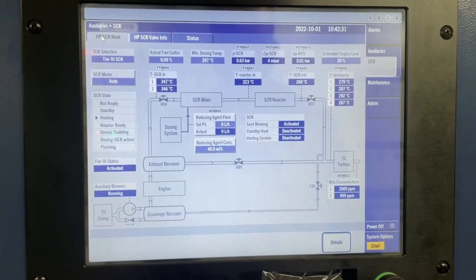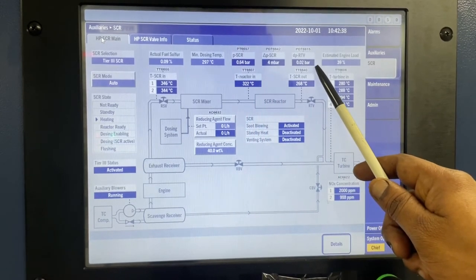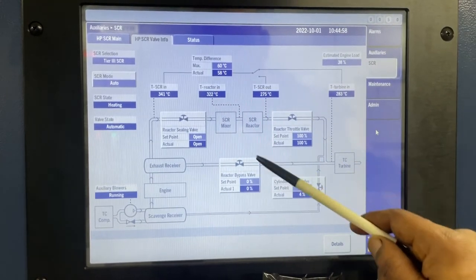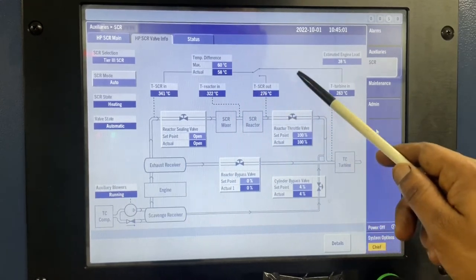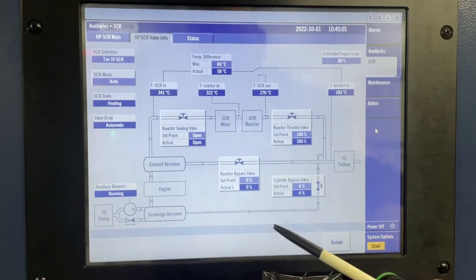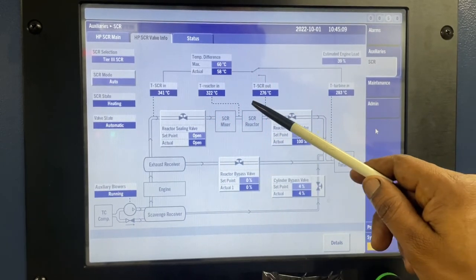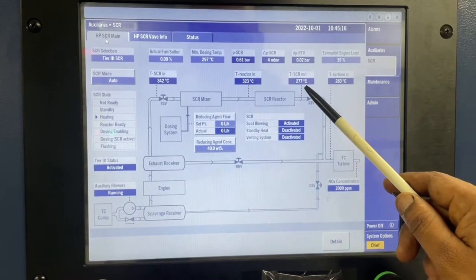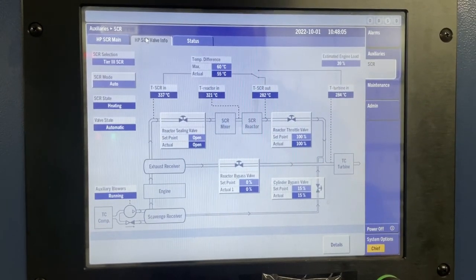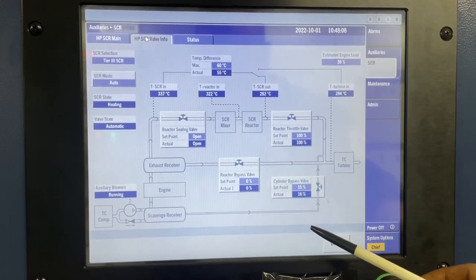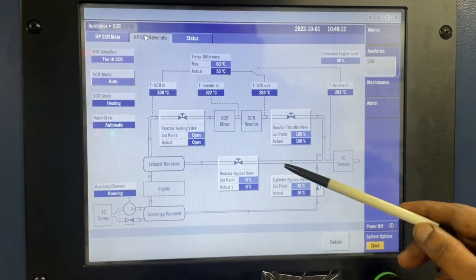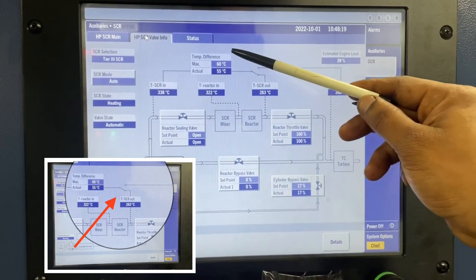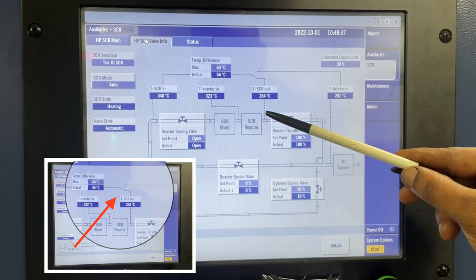The minimum dosing temperature ensures that there is no sulfuric acid condensation. As mentioned in my SCR valve function video, the CBV function is to bring up the SCR temperature. When RTV is fully open and RBV is closed, the CBV starts to open to bring the SCR reactor to dosing temperature. When CBV opens, the temperature difference calculation is taken between the SCR reactor inlet and SCR reactor outlet. You can see this on the toggle switch, which switches to SCR reactor outlet temperature.